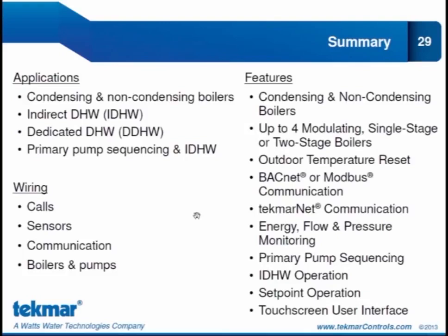We looked at the performance monitoring capability of this control, and how we can measure energy, flow, and pressure and report those performance indicators back to a building automation system so that building owners can confidently manage their buildings from a distance. We looked at how the primary pump sequencing function is a little bit different in the 284 in that it has 2 attempts this time, so that we make sure that before we shut that system off, there is indeed a problem. We tried twice.